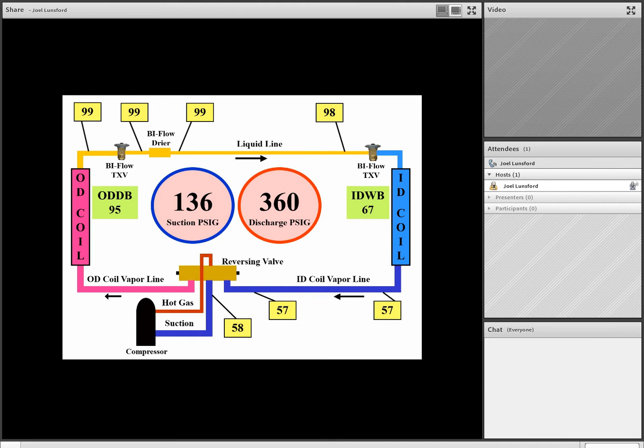As we take a look at our discharge pressure, 360 pounds of pressure, we see that we have a pressure temperature conversion of about 111 degrees, and the temperature of the liquid line leaving the warm outdoor coil in the cooling mode of operation is 99 degrees. And so at that particular point, we're looking at approximately 11 to 12 degrees of subcooling, which is normal. So the suction pressure is normal. Liquid pressure is about normal. Subcooling is normal. Superheat is about normal.